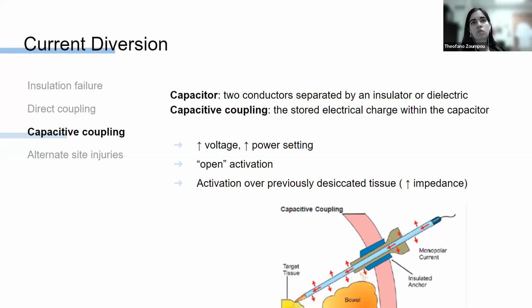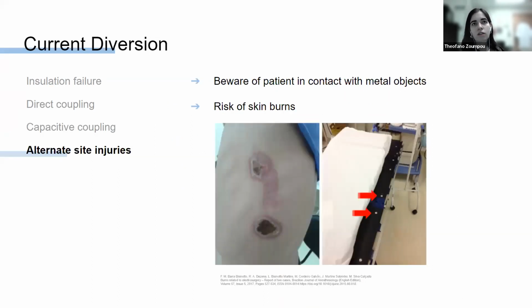In general, the risk of causing injury by capacitive coupling is higher when we use higher voltage or higher power settings. When we activate an open circuit, when the electrode is not touching the tissue, for example, as well as when we activate our device over desiccated tissue, because this tissue has higher impedance to current flow, and it is easier for the energy to escape by capacitive coupling. Alternate site injuries are another type of current diversion, and they can occur anywhere on the patient's body, sometimes on multiple sites, depending on where the current flows, essentially. And to prevent this, it is crucial to make sure that the patient is not in contact with anything that can potentially conduct current. In this case, the patient was in contact with these metal parts of the bed, and he suffered the thermal injuries that we can see.